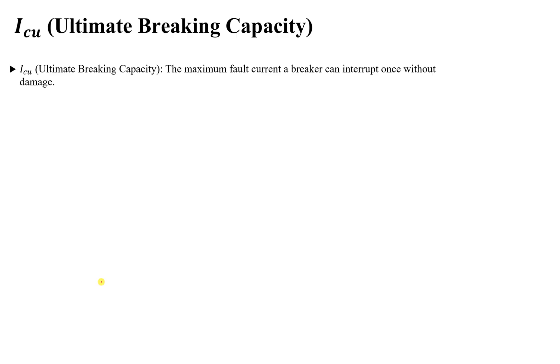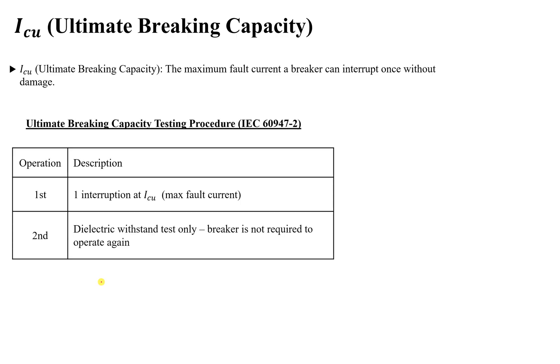After that one interruption, the breaker cannot be used again. It can interrupt without being damaged, without causing fire, without any issues, but we cannot use it again — that's why it's called Ultimate Breaking Capacity, the worst case that can happen. Per IEC 60947-2, which covers industrial circuit breakers and industrial applications, the testing procedure for ICU is as follows.